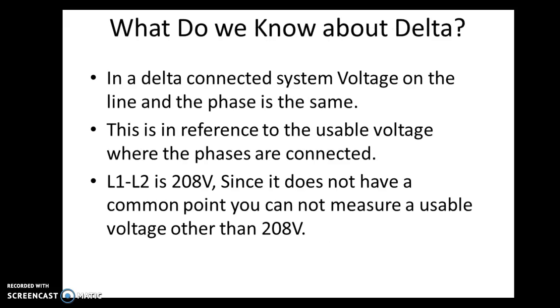We're going to first talk about some of the characteristics of a delta system and things that we should already be familiar with. So we know that in a delta connected system, voltage is constant from line to line and phase to phase, seeing how it is all the same. It's basically connected in a triangle configuration with the beginning and the end closing to make the delta. We use this in the voltage reference in talking about the usable voltage.